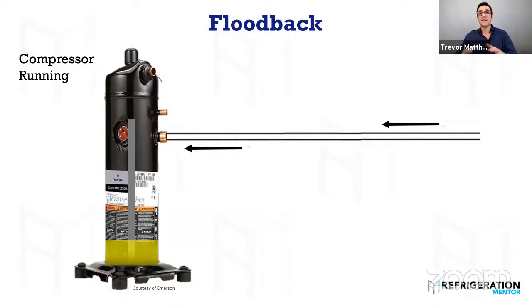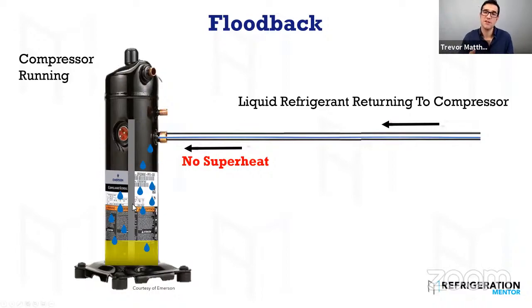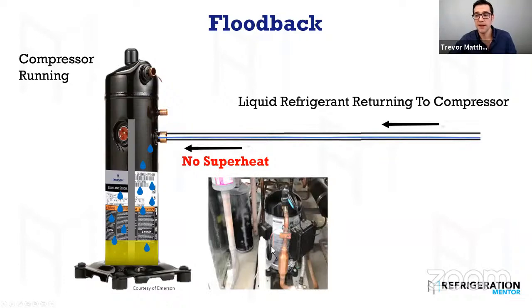Okay, floodback. Compressor is running. And this is when you have oil, everything looks good, everything's running good, but boom, liquid refrigerant starts to return to the compressor while it's running. That evaporator is not boiling off the refrigerant. And this is a great segue to the question that was just asked, because if you're flooding the evaporator, that liquid may make it back to the compressor. This is where there's no superheat, 0K, 0F right there. And it sometimes looks like this. But even if it looks like this, you don't always know. You need to check your superheat. You need to put your gauge on there. You need to put your temperature probe on to figure that out.